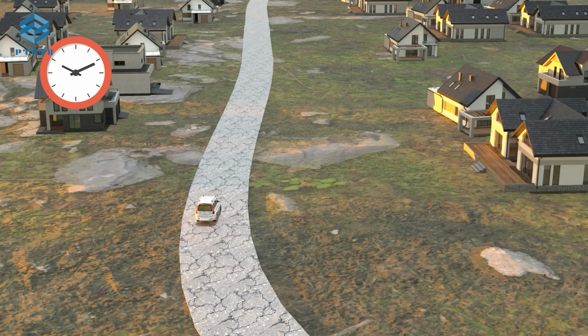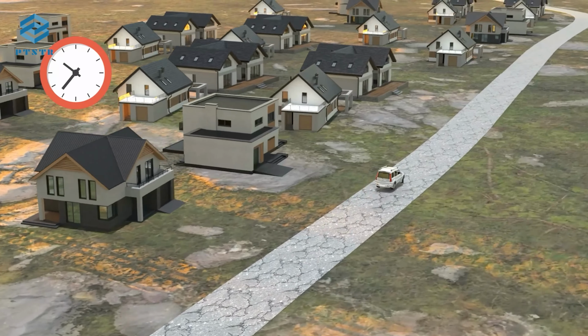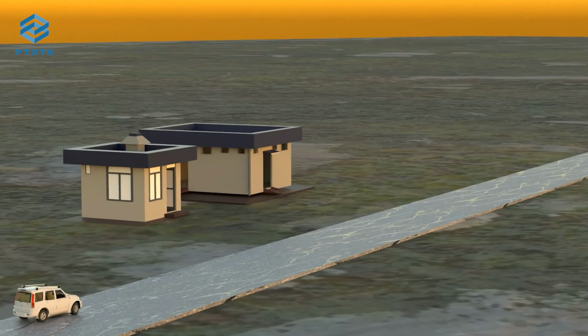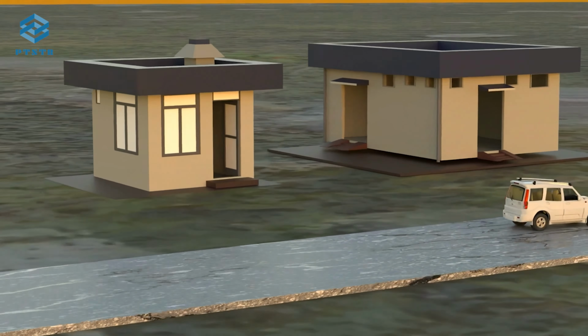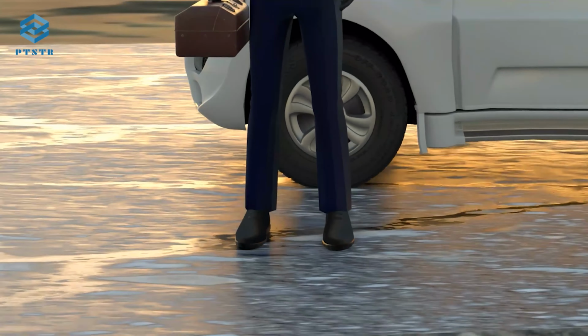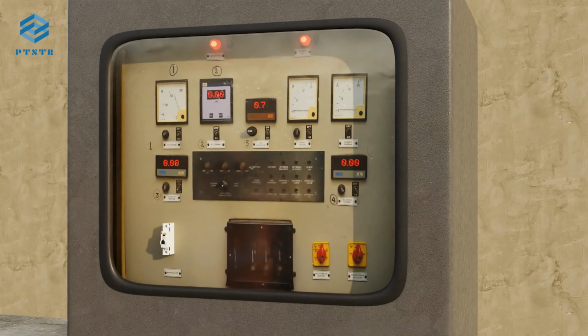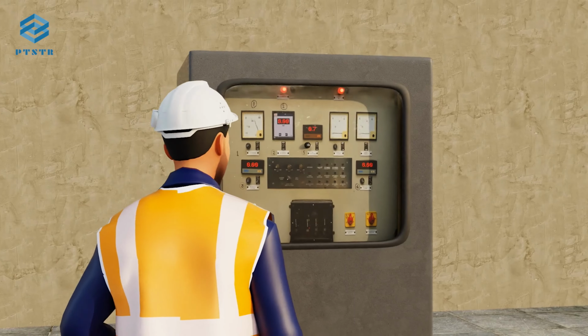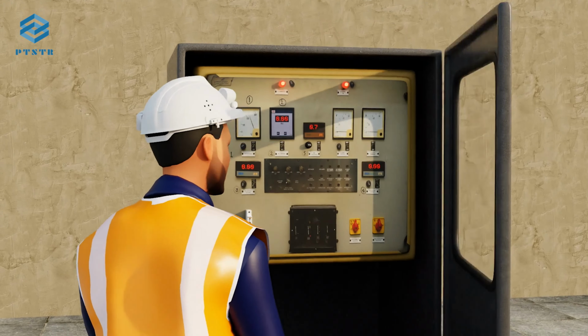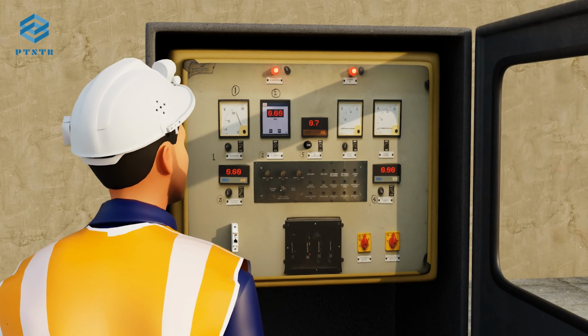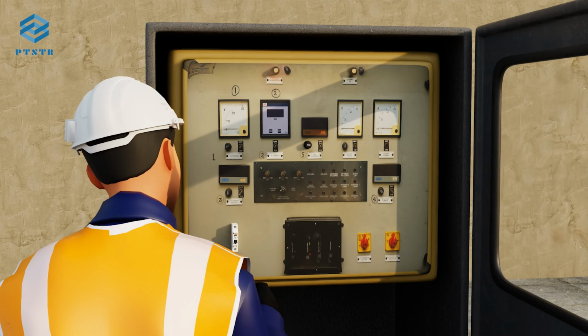In the conventional inspection process, the IOCL technician visits the TRU site, navigating through remote areas, often taking more than 2 hours to reach the site. While inspecting, it was observed that DC voltage and DC current readings were 0 and the PSP voltage of the pipeline was minus 0.7 volt with respect to copper-copper sulfate reference electrode. That means the pipeline is cathodically underprotected. Further, AC supply was available.